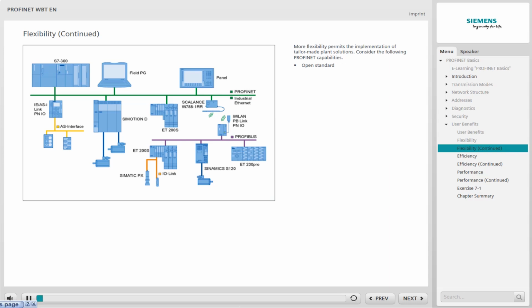Due to its openness, PROFINET provides the basis for a uniform automation network and thus allows the easy integration of existing systems. PROFINET permits the unrestricted parallel use of an Ethernet connection for I/O communication and standard IT data TCP/IP. New PROFINET segments can be integrated without any problem into existing plant or machine infrastructure, regardless of the manufacturers used. For PROFIBUS users, there is maximum investment protection because existing PROFIBUS system parts can be seamlessly integrated into PROFINET. Since PROFINET supports TCP/IP, it permits the use of standard web services such as web servers in field devices. Machine downtimes are significantly reduced thanks to quick access to diagnostic information via web servers.